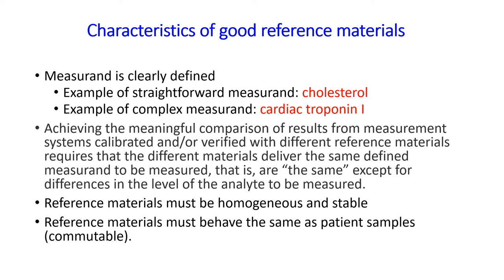Achieving the meaningful comparison of results from measurement systems calibrated and/or verified with different reference materials requires that each of the different materials delivers the same defined measurand. The goal of any standardization effort is to provide measurements that are stable and consistent across time and space. To achieve this, the reference materials used must be both homogeneous and stable with respect to one or more specified properties which have been established to be fit for their intended use in a measurement process.